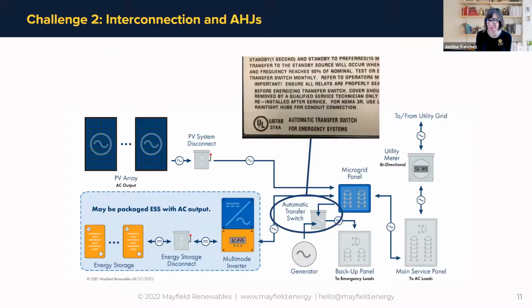This whole change happened because the AHJ said, hey, this is an emergency system, your stuff has to be emergency rated. This caused a complete redesign on our side, and we had to remodel everything as well, because we had always assumed the generator would be able to charge those batteries.